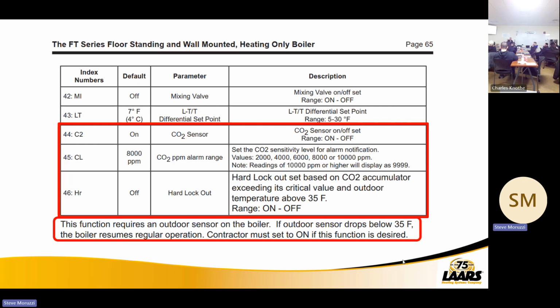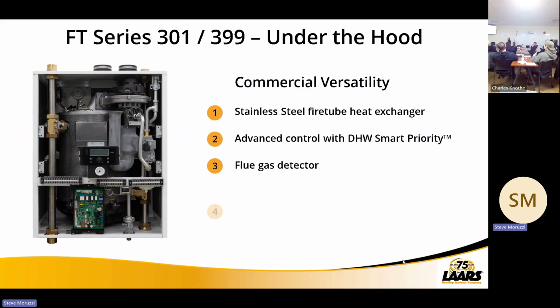And at night, if that temperature drops to 21 degrees or anything below 35 degrees, that boiler comes out of lockout, will at least protect the building from freezing. Okay. Next day, temperature goes up above 35, it goes back into hard lockout. So you have that option. We are not defaulting that in the on position, okay? Off position is default right now, is just going to register on the home screen, all right? So we can protect that heat exchanger, if you will.